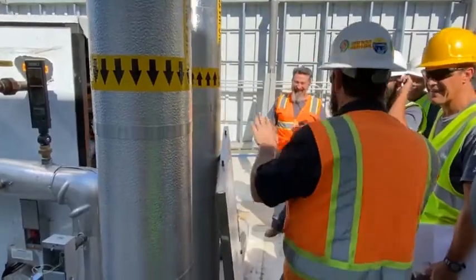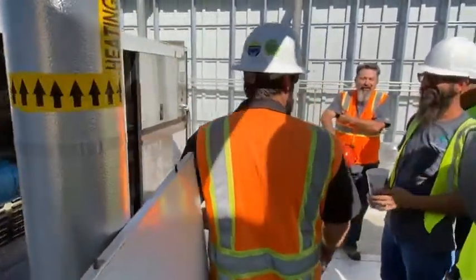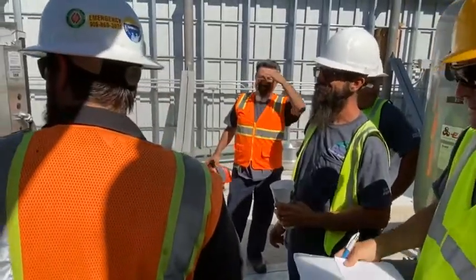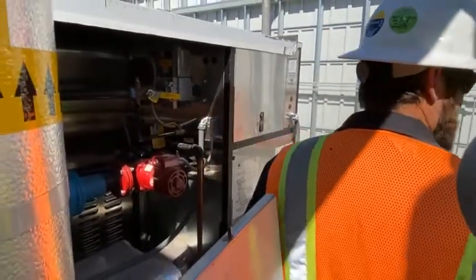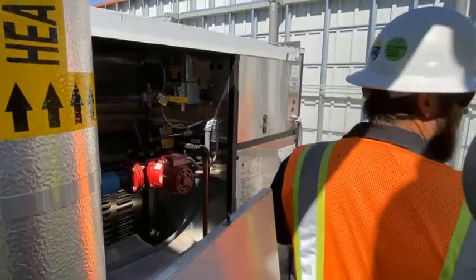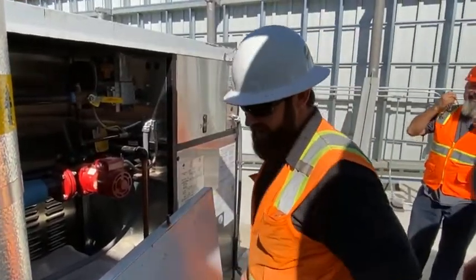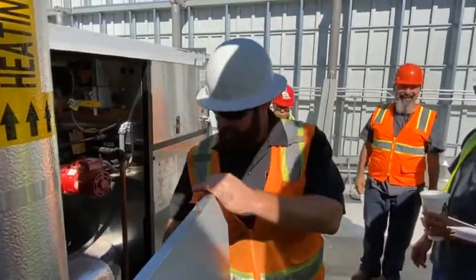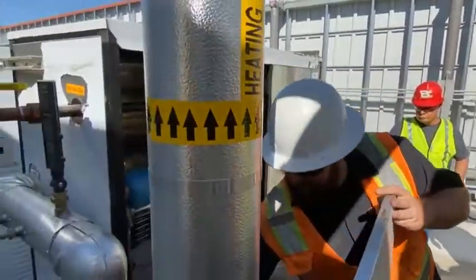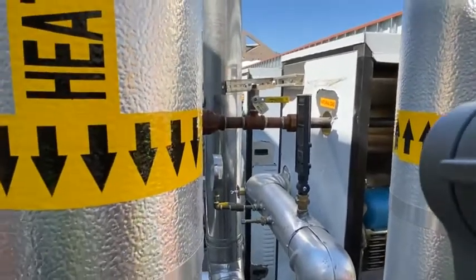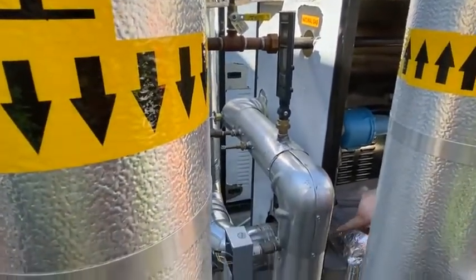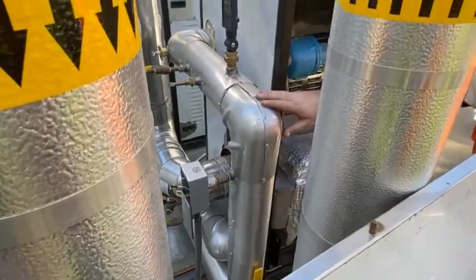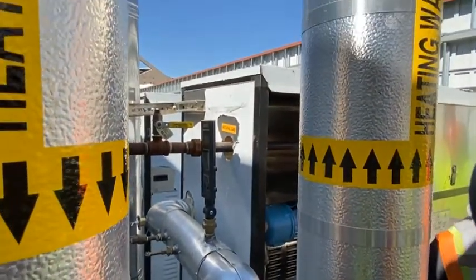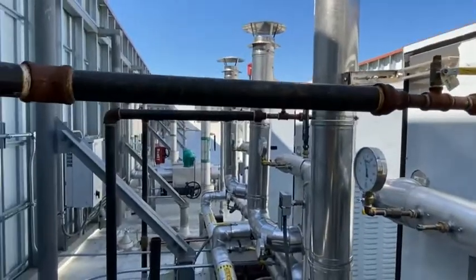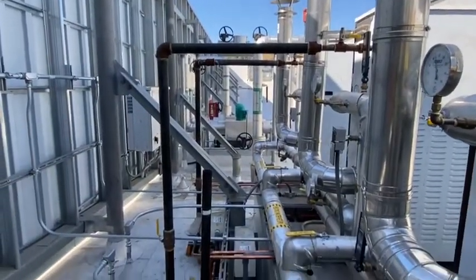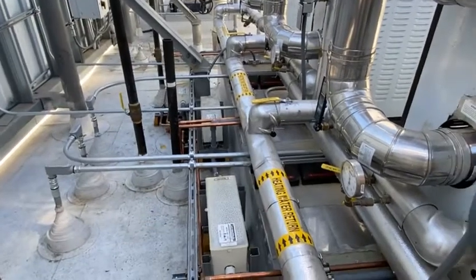I like these because they're very easy to work on. For adjustments, just here and here, super easy to do. Jeremy, don't touch that, please. They are at a specified level already. Then we got our isolation valves here on the water side, and the other one's going to be on the outlets, over on the other side. We went over the shut-off valves on the units yesterday. The lower pipe is the inlet. It has a strainer.